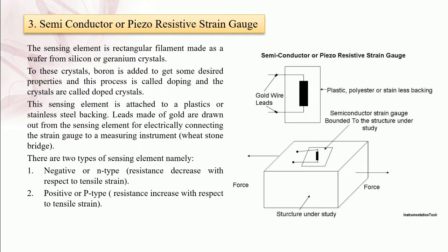These gauges are used where a very high gauge factor and small envelope are required. For semiconductor strain gauges, semiconducting materials such as silicon and germanium are basically used. A typical strain gauge consists of a strain sensitive crystal material and leads that are sandwiched in a protective matrix. The production of this gauge employs conventional semiconductor technology, using semiconductor wafers or filaments which have a thickness of 0.05 mm and bonding them on a suitable insulating substance such as Teflon. Then gold and lead are generally applied for making the contacts.